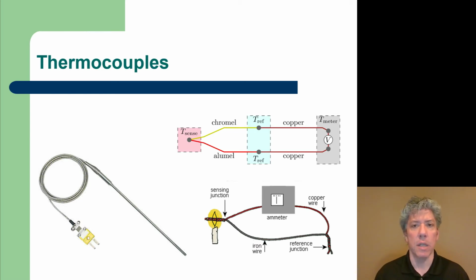And if you actually set this up as an experiment, it turns out that if you put an ammeter in line with the copper wire or with the iron wire, you could measure current flow. Now the amount of electric potential in volts that is generated because of the difference in temperature between the flame end and the reference end, that amount of current and voltage would be pretty small. But it can be measured, and it turns out that the voltage is pretty much proportional to, or dependent on, the difference in the temperature between the two points.